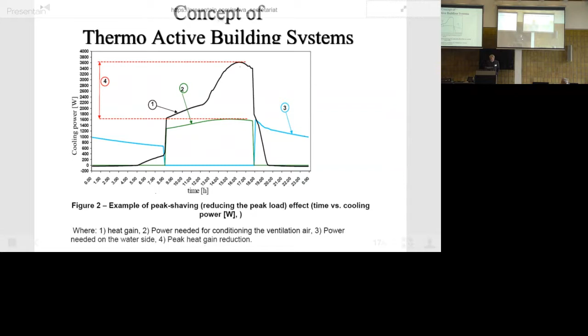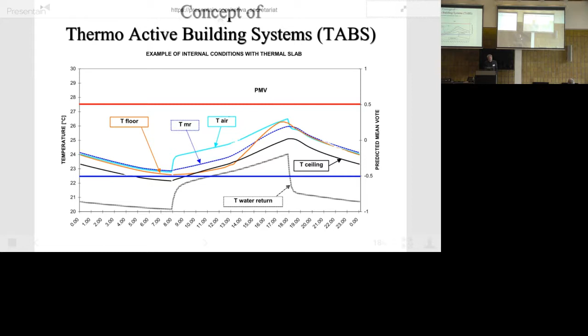Then during nighttime, you don't need to ventilate that much. You start now cooling on the slab, and you circulate water there. And then the idea is that the area under these curves here should be the same or higher than the area under the load. And the other thing is that you need to make sure that, for example, the operative temperature in the space is within the comfort range, or the PMV values are within plus minus 0.5. So basically, you let it drift within that range. And that was also the measurement from the first building we made, showing that you do that.